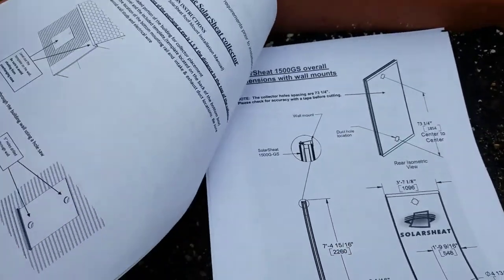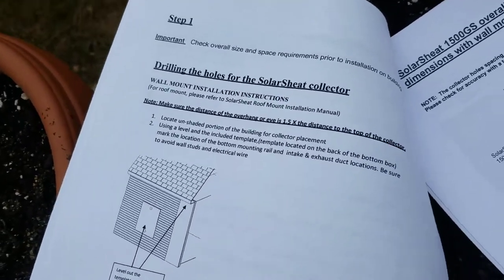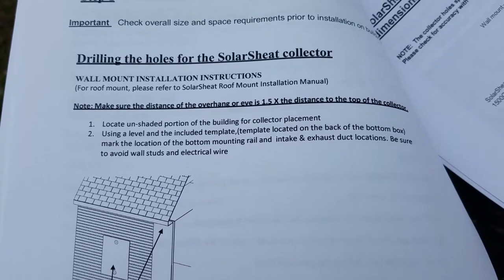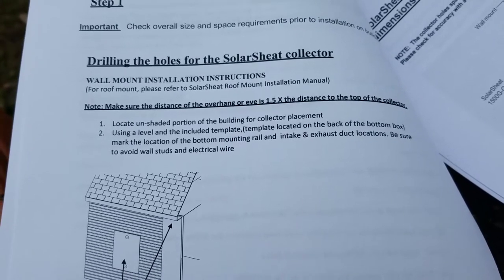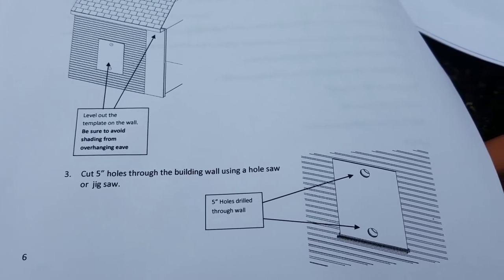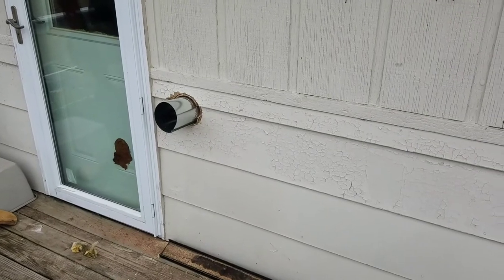Drilling the holes for the SolarSheat collector: locate an unshaded portion of the building for collector placement. Using a level and the included template — located on the back of the bottom box — mark the location of the bottom mounting rail and intake and exhaust duct locations. Be sure to avoid wall studs and electrical wire. Level out the template on the wall and avoid shading from overhead eaves. Cut 5-inch holes through the building wall using a hole saw. We're gonna do that now — I'll get this all leveled and go from there. We are back — I have the wall all cut open.